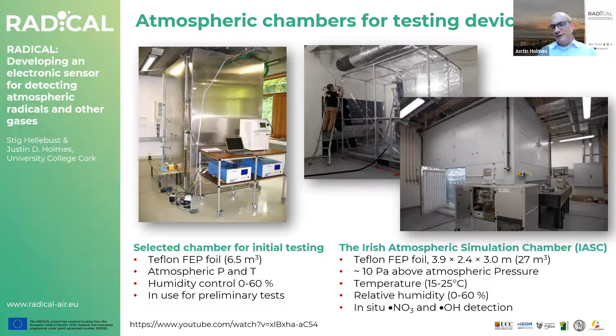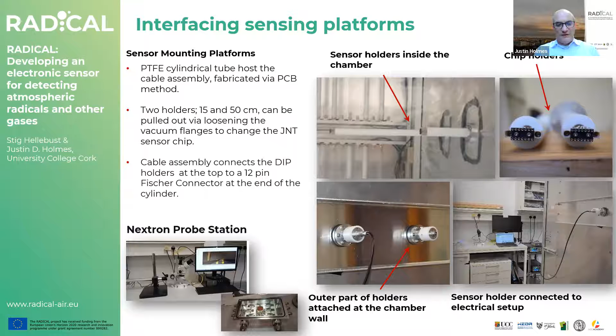So these are the ways that we interface with the chamber. There are these sensor mounting platforms, which are printed circuit boards, and we just attach them into our chip holders, and then we have these rods which go inside the chamber. The cables connect to our electronics, and then we can measure a signal. We also have an Nextron Probe Station, which is not much used for radicals, but is useful for other gases, where we can flow gases over a chip with electrical probes and measure a change in the conductivity or other parameters within our device. So those are the two setups that we're using at the moment.